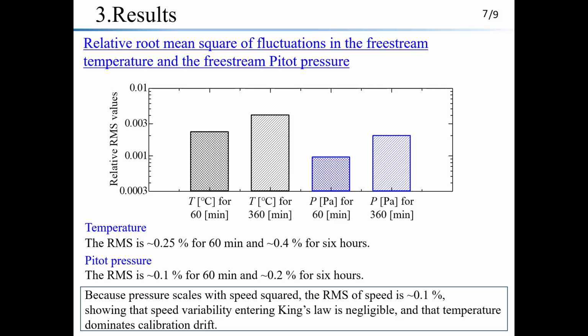The figure compares the relative RMS of the freestream temperature and Pitot pressure. For temperature, the RMS is within 0.25% for 60 minutes and within 0.4% for 6 hours. For pressure, it is within 0.1% and within 0.2%. Hence, temperature fluctuations are roughly twice those of pressure. Because pressure scales with speed squared, the RMS of speed is within 0.1%, showing that speed variability entering King's law is negligible, and that temperature dominates calibration drift.